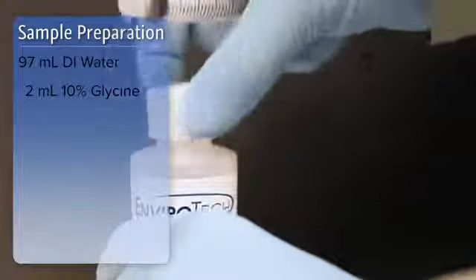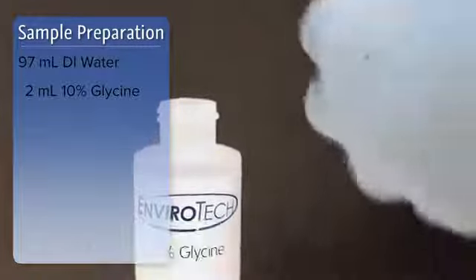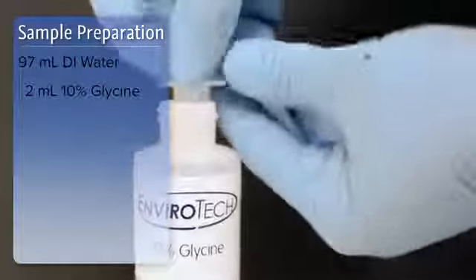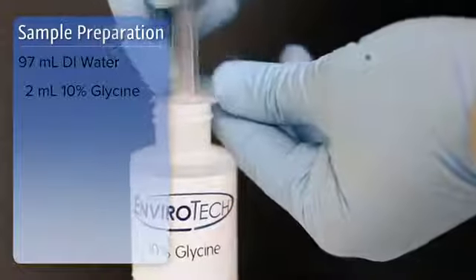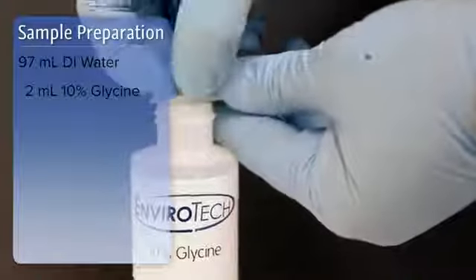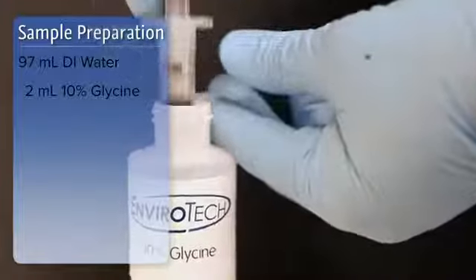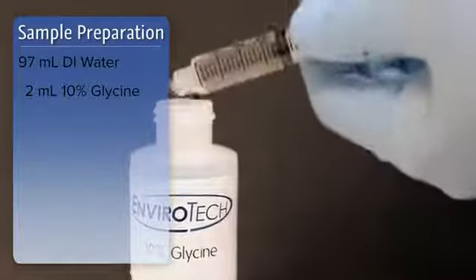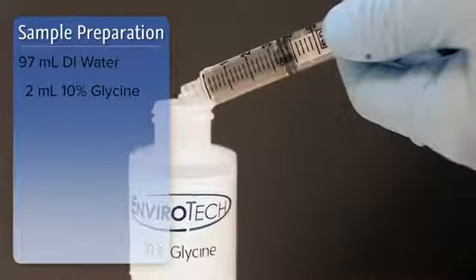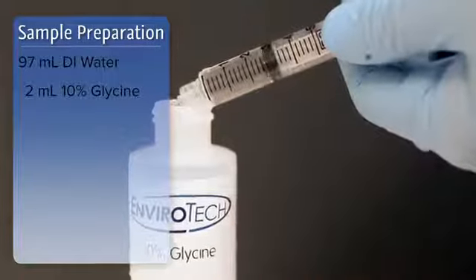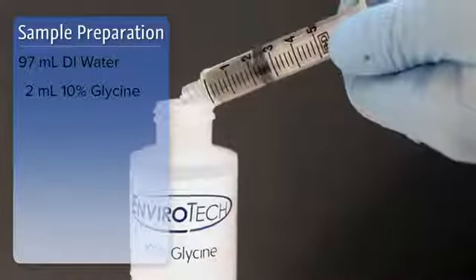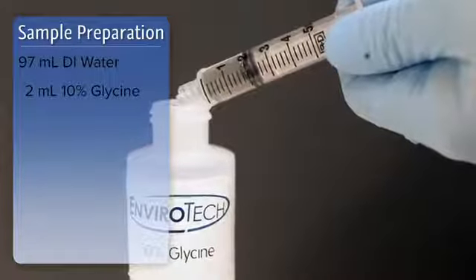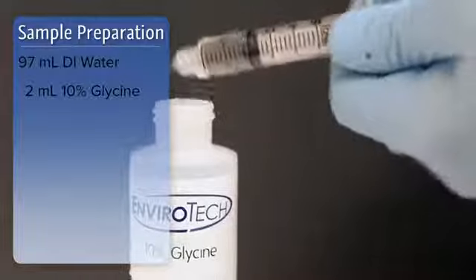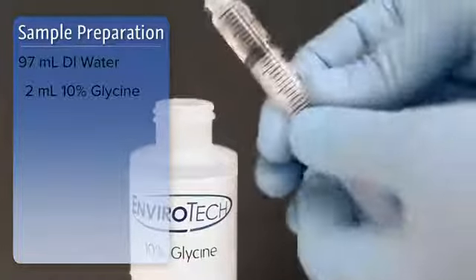Activation of HB2 with sodium hypochlorite bleach means there is a possibility that some of the halogen may be in the form of hypochlorous acid or hypochlorite, and some in the form of hypobromous acid. Clearly, it is desirable to have all of it in the form of hypobromous acid, and minimize or eliminate the amount of hypochlorous acid, hypochlorite ion present.